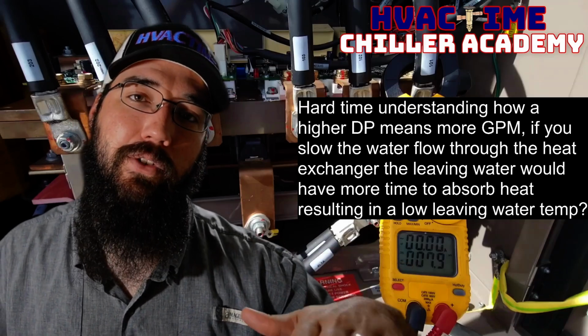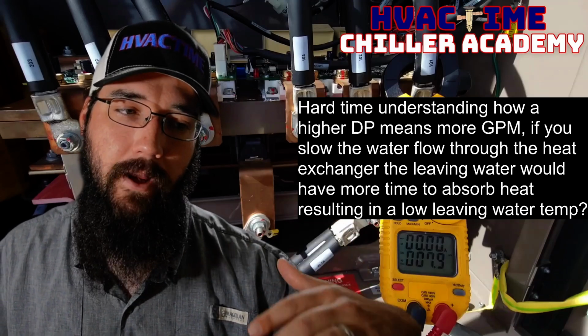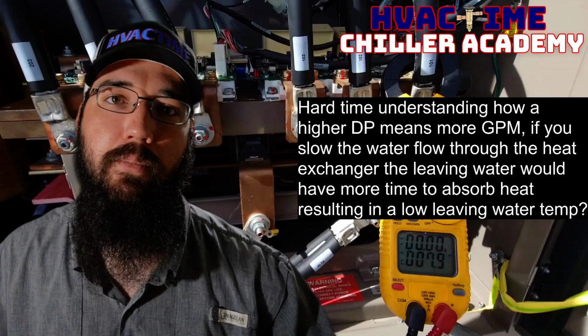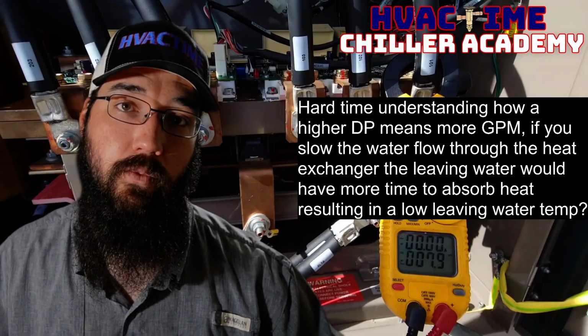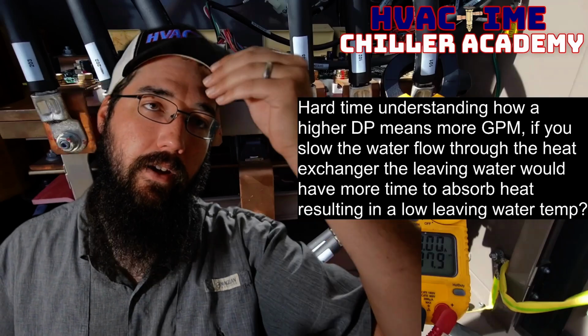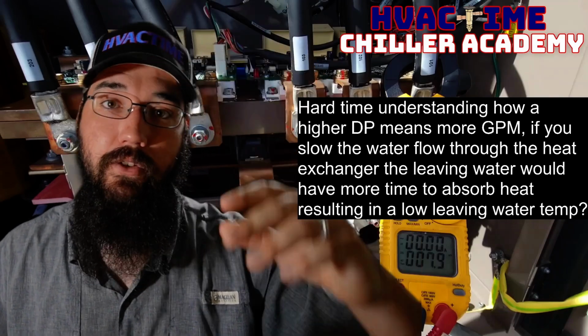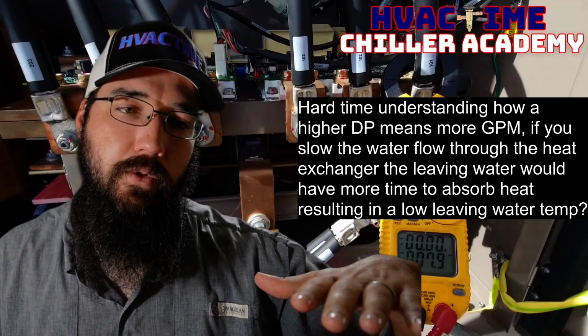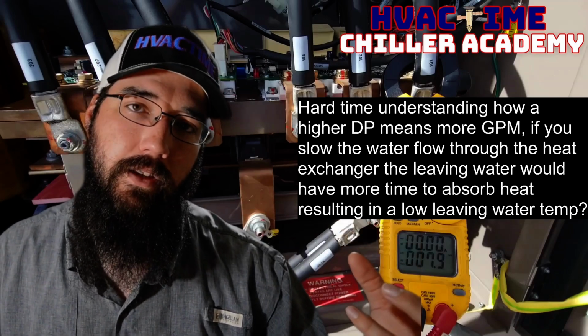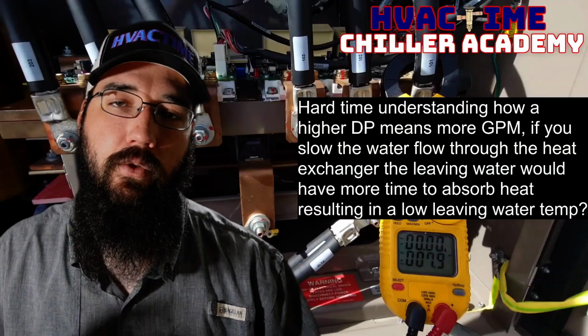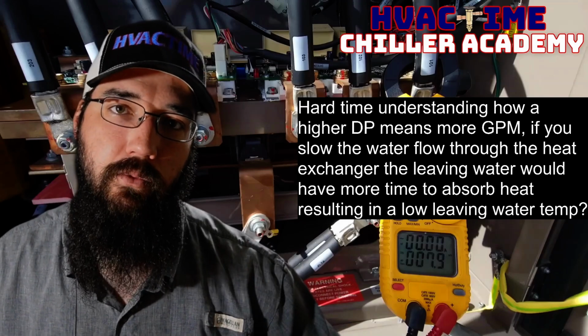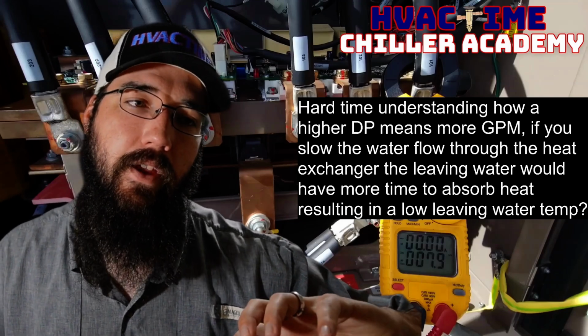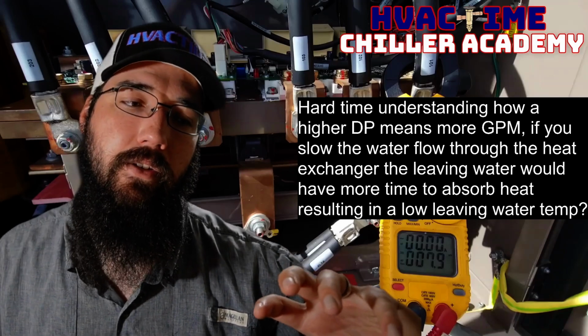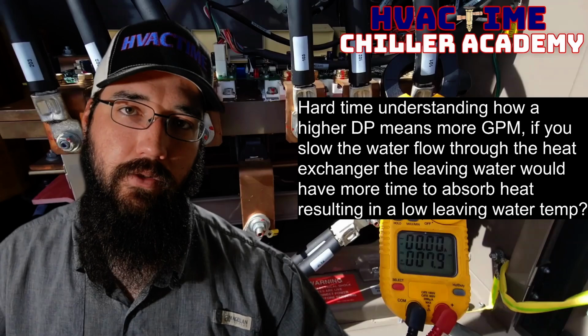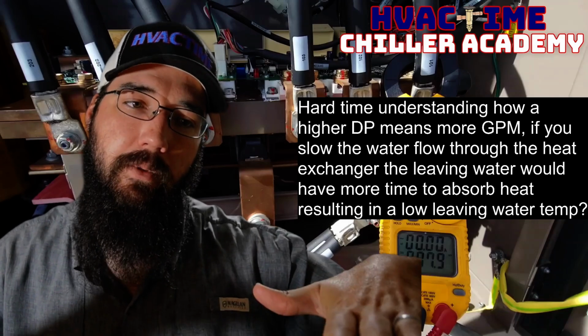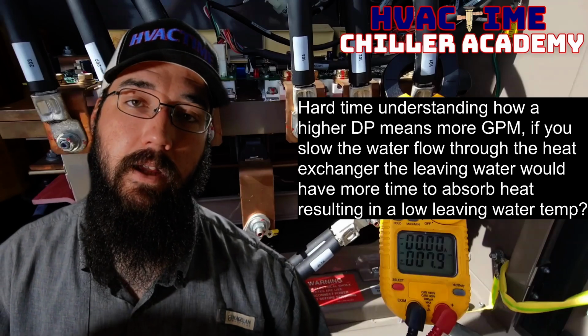So we can force so much flow through the heat exchanger that ramping that compressor as much as we can't make set point properly, or we're pushing the compressor way past where we should to get there. And so I've had that where you start having these crazy approach values, and it's because we're trying to overstage the compressor in order to get the water temperature down because we have so little contact time. So the water is moving so fast, with such a high GPM through the heat exchanger that we don't have enough contact time. And it ends up forcing the compressor to stage up higher, which ultimately will force our saturations to drop lower, which gives us a higher approach.